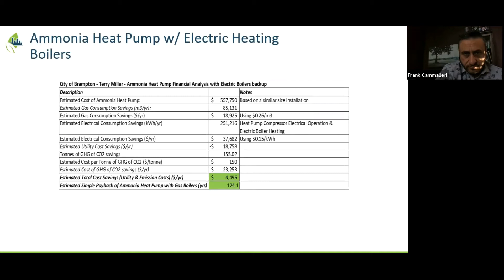A lot of this comes out to this result because the intent is to recover as much heat as you can, based on that graph you saw of heating needs of the facility versus the heating produced from the refrigeration plant. The vision is that this will just be top-up heat - the gas heating and electric heating will just be top-up heating. So if we go to the next slide.